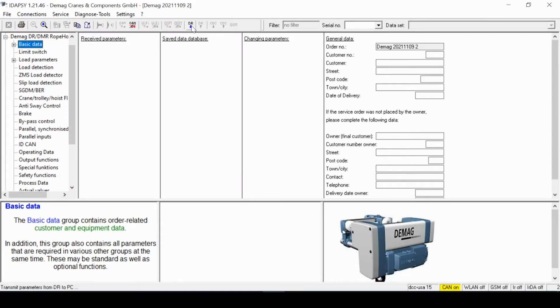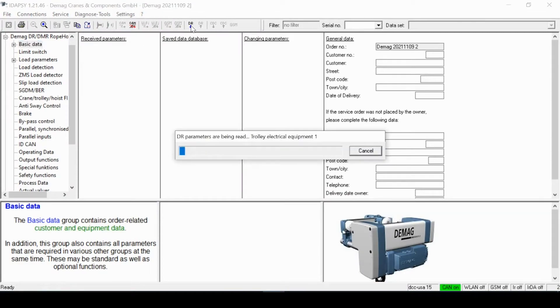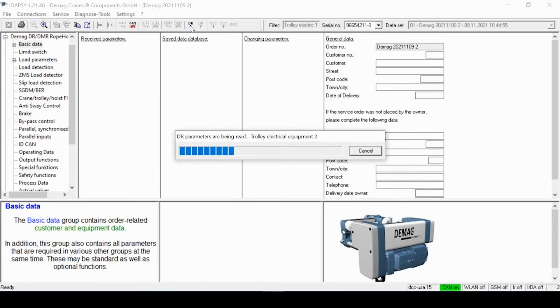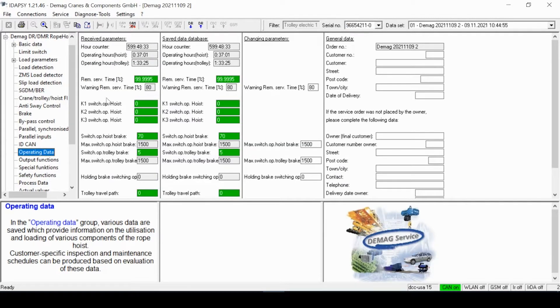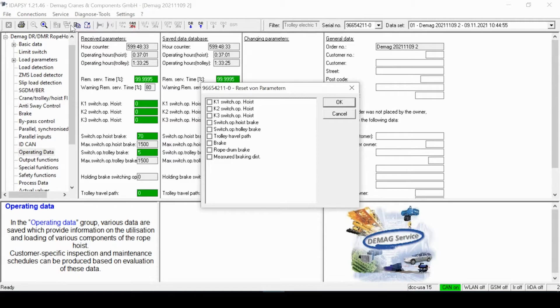I've made a connection to the crane system, completed a CAN bus connection and download for my hoist. Now that my hoist file is viewable, I'm going to open the operating data folder and then at the top toolbar, I'll pick service and then under it, reset.